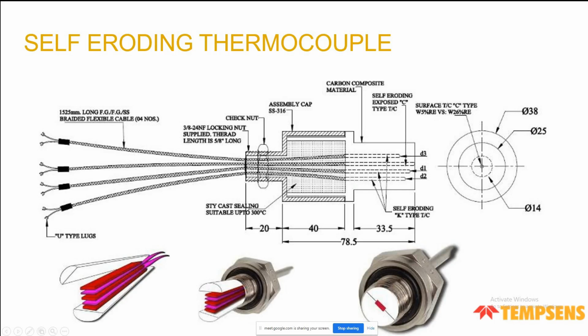You can see here there are multiple thermocouples; one of them is a self-eroding kind, and the rest are standard thermocouples. The center one is the self-eroding thermocouple, which will keep giving the temperature until it is eroded up to point D1. Such special assemblies can be done, or a single self-eroding thermocouple can also be offered for experimental requirements.